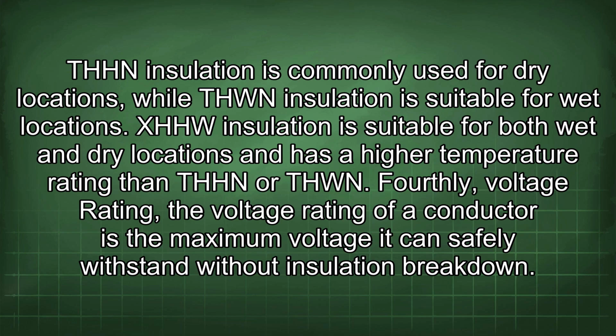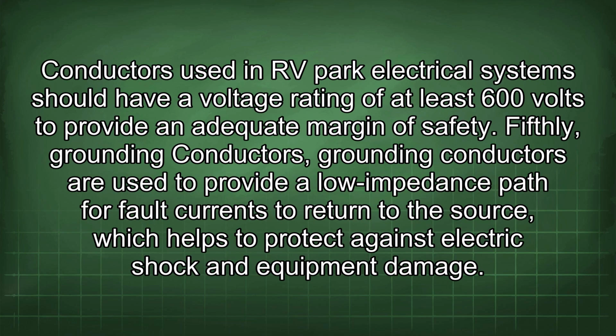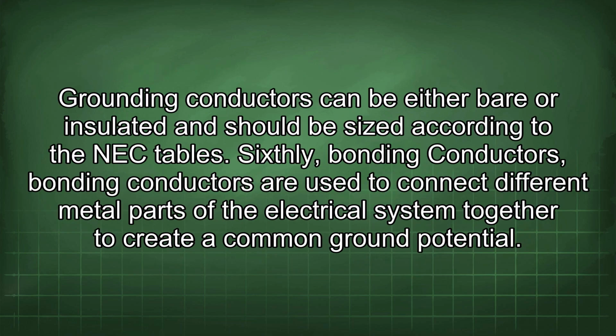Fourthly, voltage rating. The voltage rating of a conductor is the maximum voltage it can safely withstand without insulation breakdown. Conductors used in RV park electrical systems should have a voltage rating of at least 600 volts to provide an adequate margin of safety. Fifthly, grounding conductors. Grounding conductors are used to provide a low impedance path for fault currents to return to the source, which helps to protect against electric shock and equipment damage. Grounding conductors can be either bare or insulated and should be sized according to the NEC tables.